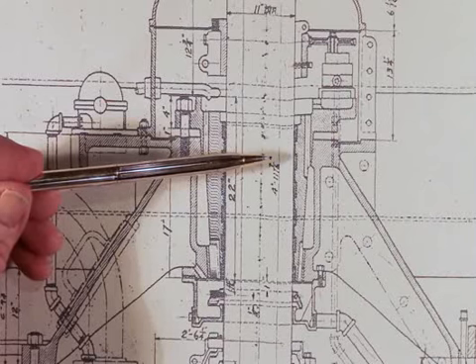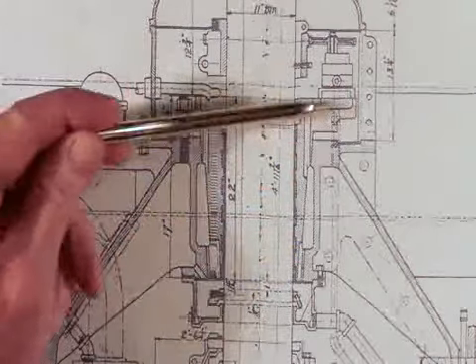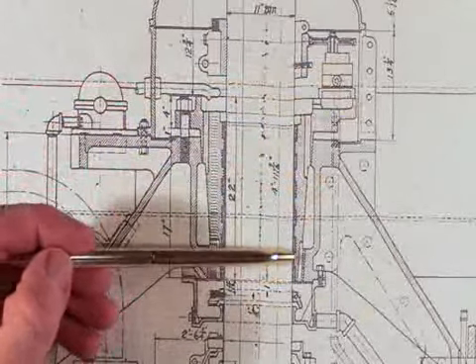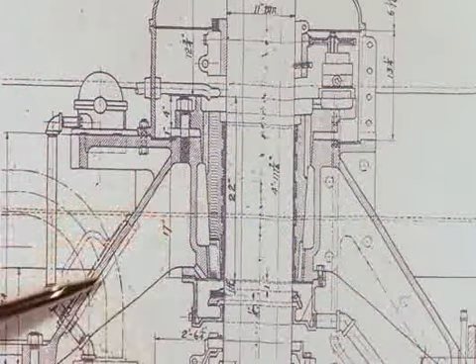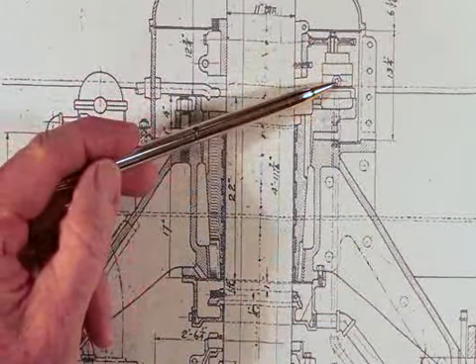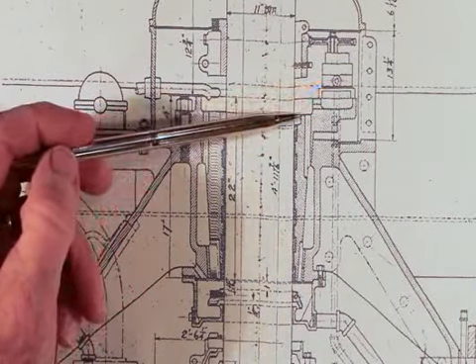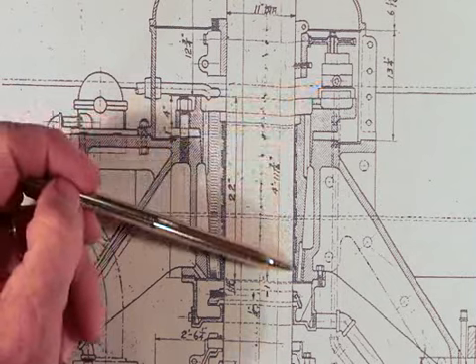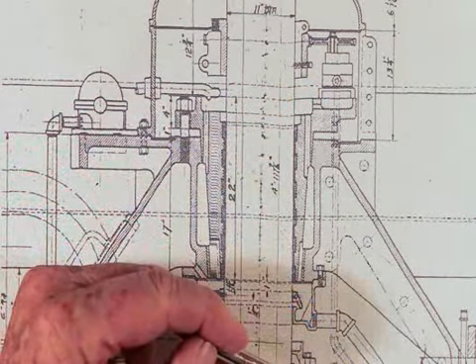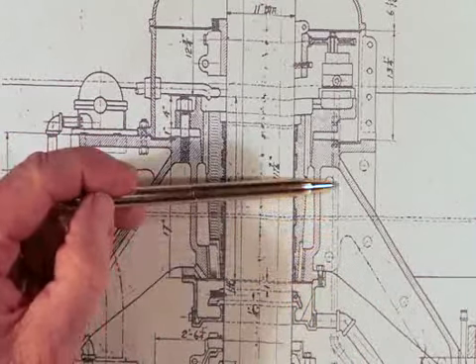The conversion plan involves removing this bearing and oil pump assembly mounted above the turbine head cover. The existing white metal bearing is contained in a cast iron carrier. This gear pump is the one that serves to supply oil to the lower bearing. Oil flows downward through the bearing, past the slinger ring, and into a containment area of the head cover, where it is conducted by this pipe back up to the pump above the bearing.